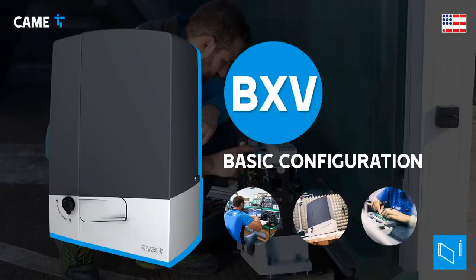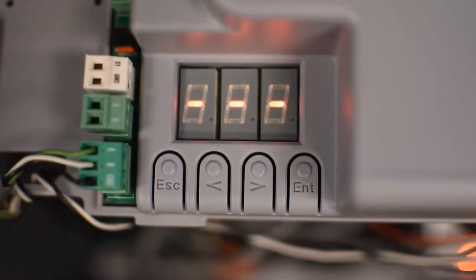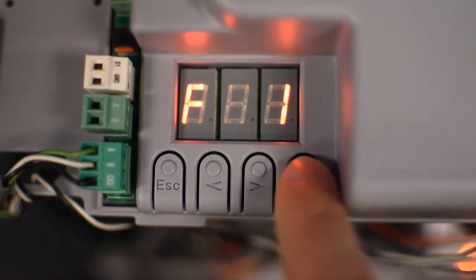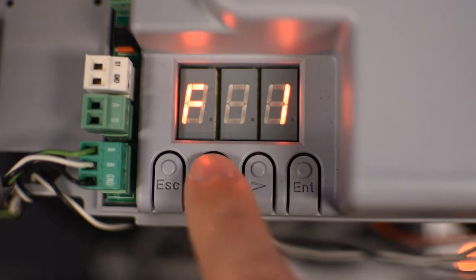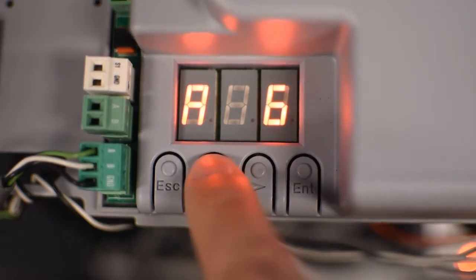In this video, we're going through the basic configuration of a CAME BXV operator. When you first power the operator, you'll see these lines blinking in the display, indicating that we haven't calibrated the encoder yet. But before doing that, you need to select the type of motor that you have. To do that, you need to press Enter to get to the menu, and use the left arrow until you see A1.